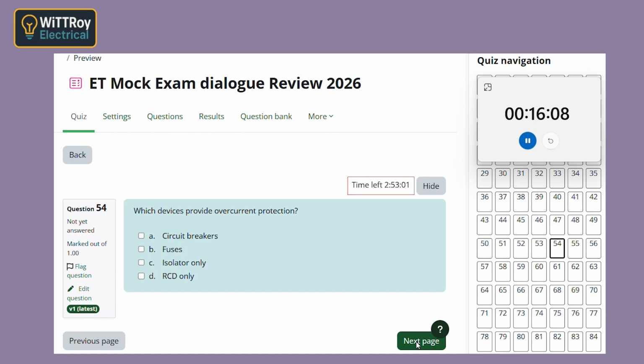Question 54. Which devices provide overcurrent protection? Fuses and circuit breakers? Correct. A fuse melts when current exceeds a certain level for long enough or during a major fault. A circuit breaker trips open. Why is RCD only wrong? Because an RCD may not respond at all to a balanced overload, so it is not an overcurrent protection device by itself. And an isolator is only for switching and isolation, not automatic fault protection.